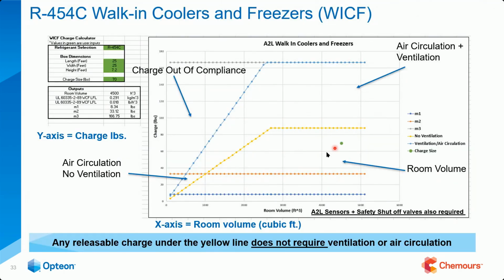All right, that would be just the room volume and room volume only. So that would be that mitigation strategy. Think about it, that is a mitigation strategy. If there's enough cubic feet of air there, you don't have to worry as much about these other safety features, as far as bringing in, circulating air or bringing in fresh air or some type of ventilation.